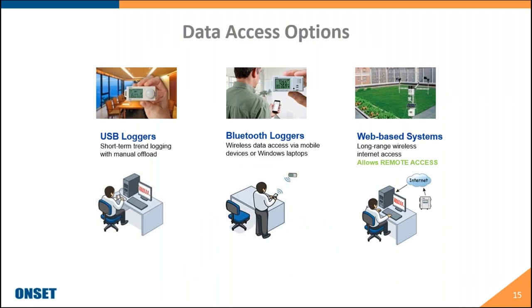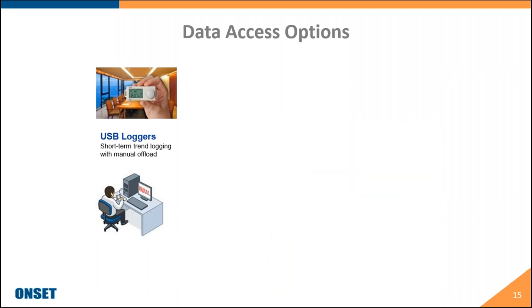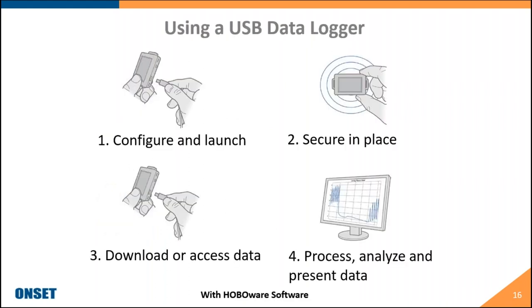There are a few ways to access data from our loggers: USB loggers, Bluetooth loggers, and web-based loggers. Our Bluetooth data loggers can be part of a remote monitoring solution. USB data loggers are ideal for short-term trend logging with manual offload — you connect a USB Mini-B cable to a computer to configure and launch the device, secure it at its deployment site, then download the data to our HoboWare software to process, analyze, and create presentation-grade reports.